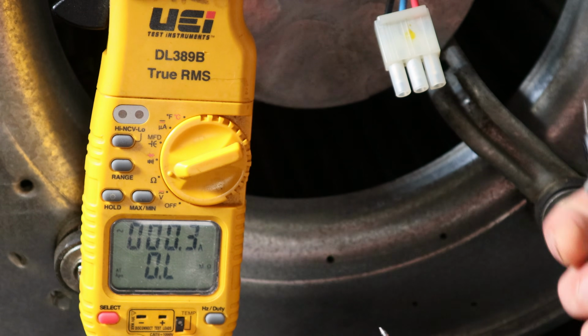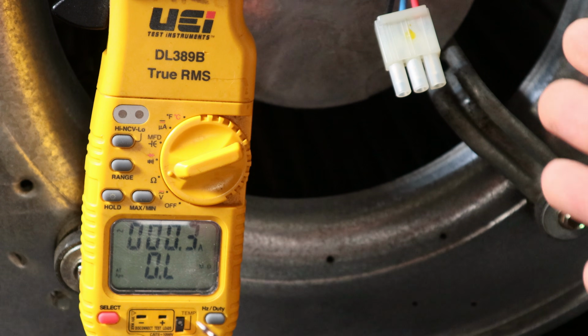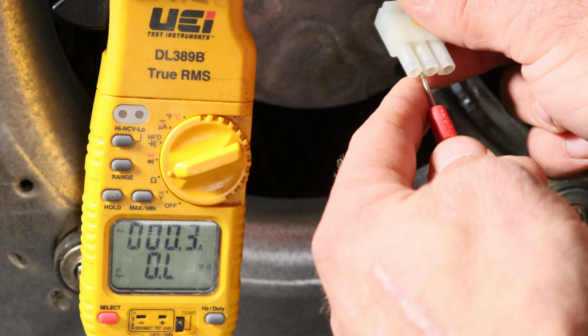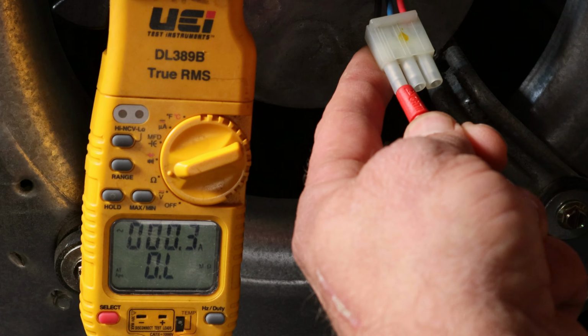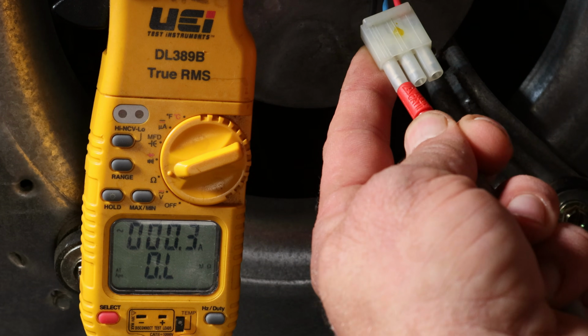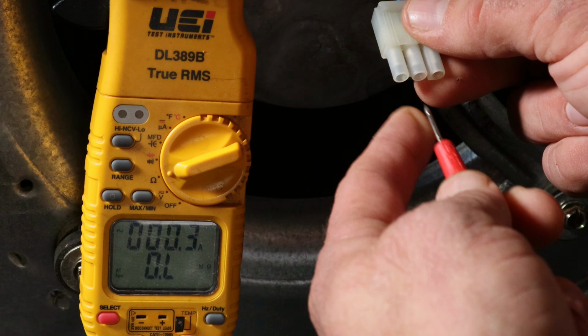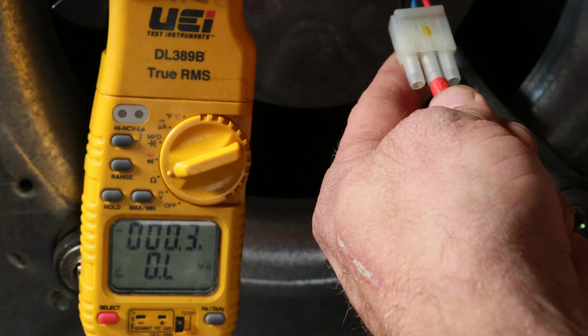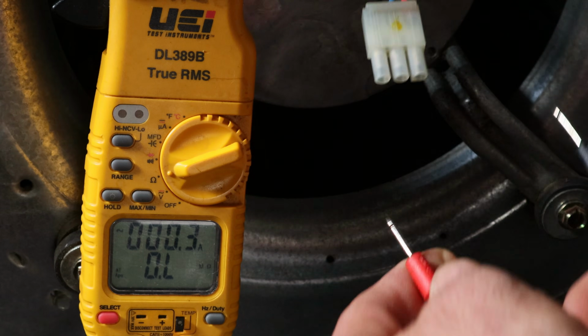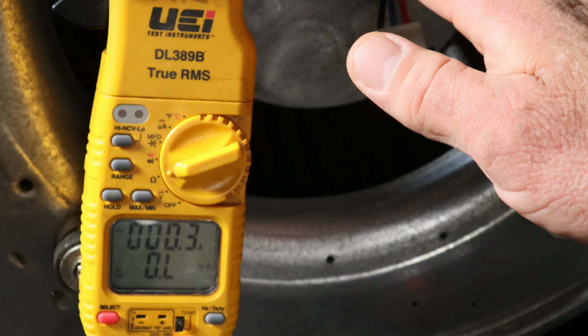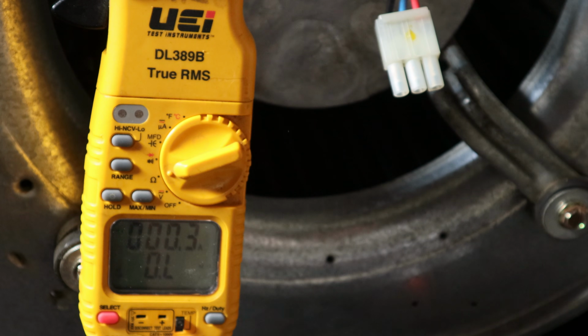What you also want to do is check each winding to ground, make sure you don't have anything shorted out. So you just do this one by one right to the grounded casing, and you should read OL. If you're reading 0, you have a shorted out winding. So everything checks out here. We know the motor is okay. And so now it's pretty much down to the module being bad.